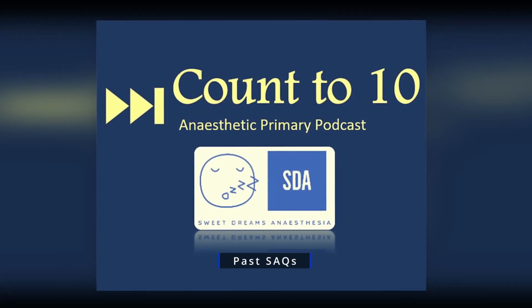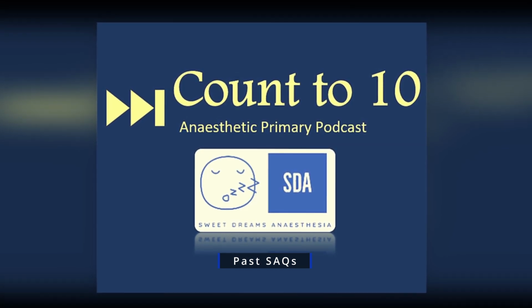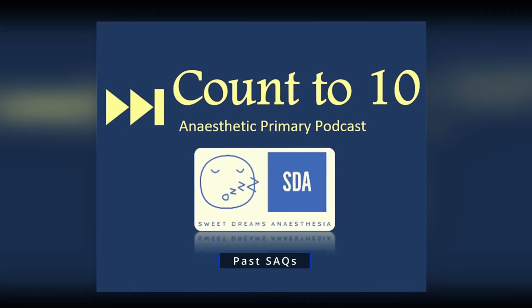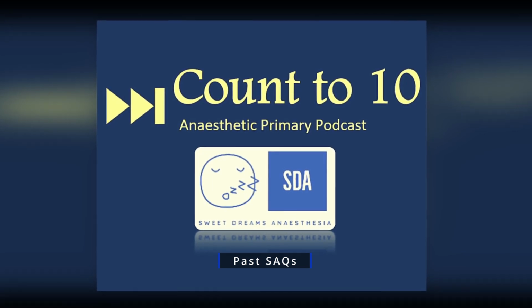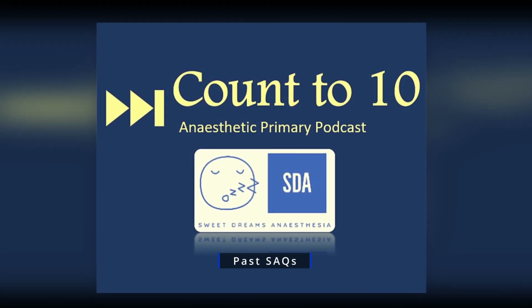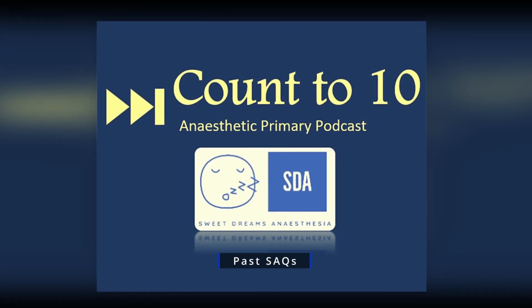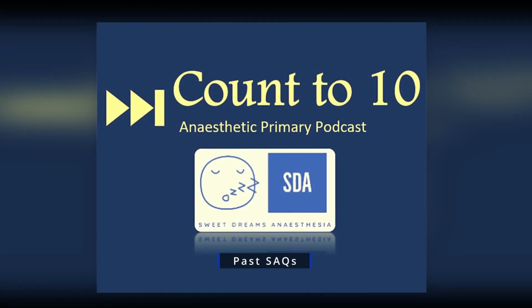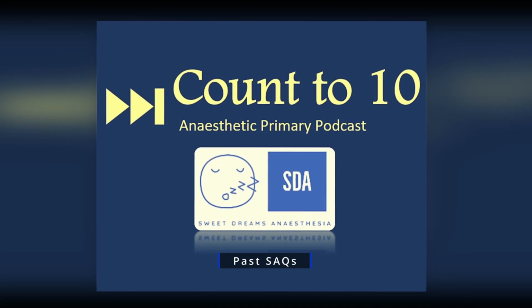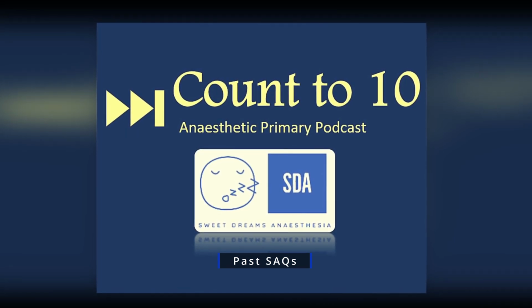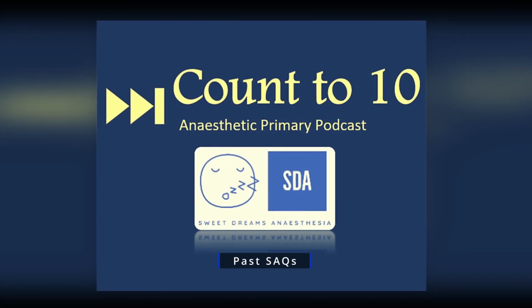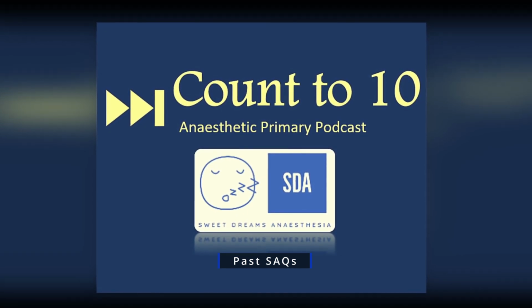Finally, in terms of errors that can happen outside the machine, I like to think of this as either happening from the patient or from external sources. So the easiest one is that the patient can shiver. Now all of a sudden, the oscillations and amplitudes are hard to detect, and therefore an output can't be delivered. The other issue is if someone's leaning against the cuff or moving the patient's arm. This also leads to the same effect and leads to an inaccurate reading.